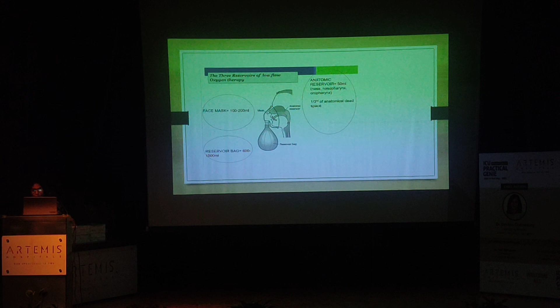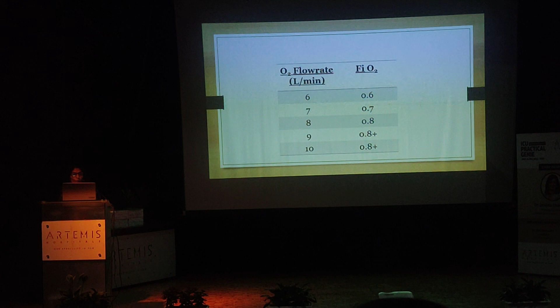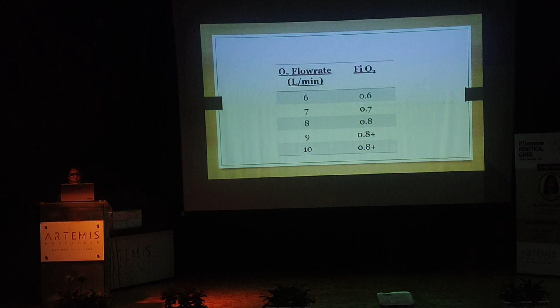The partial rebreathing mask provides an FiO2 of 0.6 to 0.8. A minimum of 8 liters of flow is required to enter the mask to remove the exhaled CO2 and refill the oxygen reservoir. The flow rates must be sufficient to keep the bag at least 1/3 to half inflated at all times. This diagram shows how the inspired and the expired gases mix. The FiO2 achieved at 6 liters is about 0.6, at 7 about 0.7, and even if you go on increasing beyond 8, the FiO2 remains at 0.8.